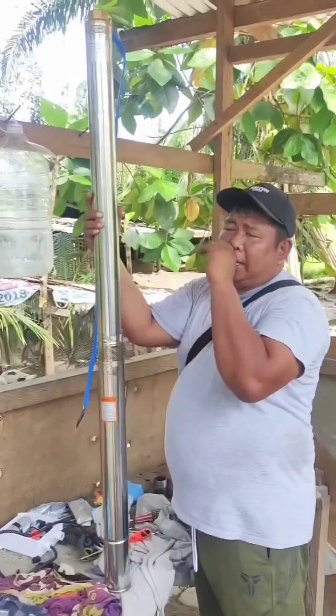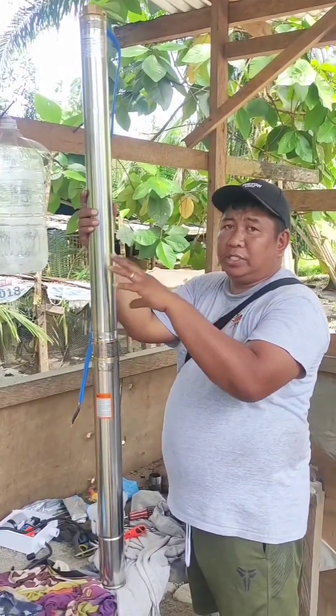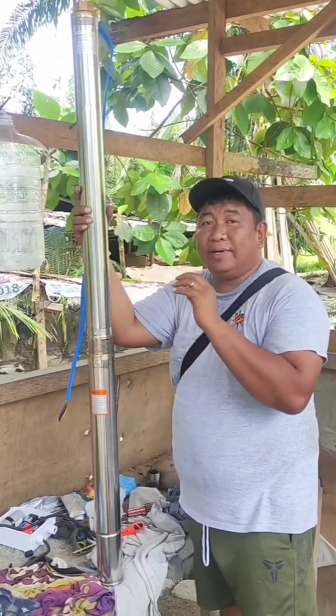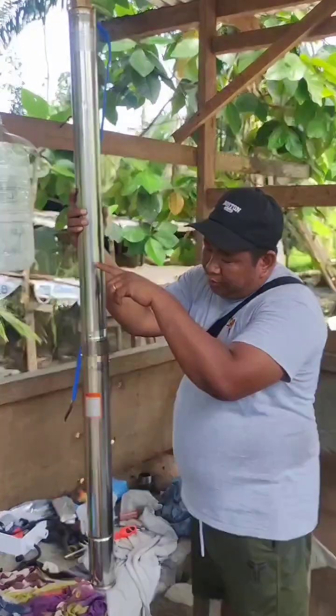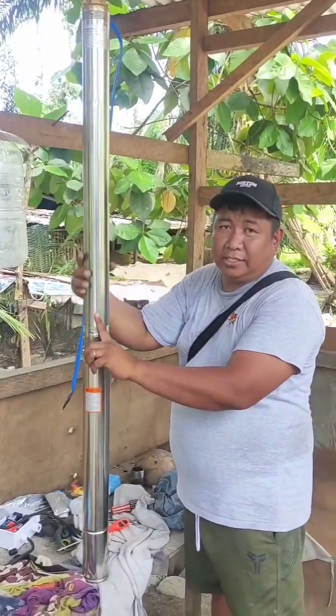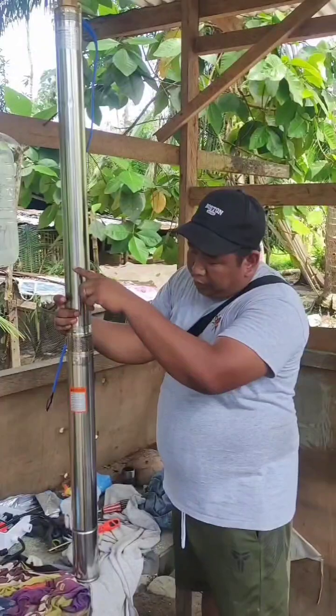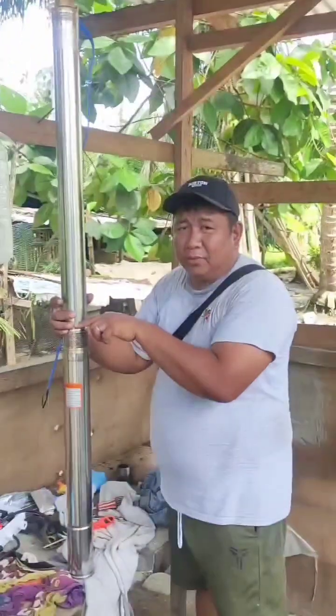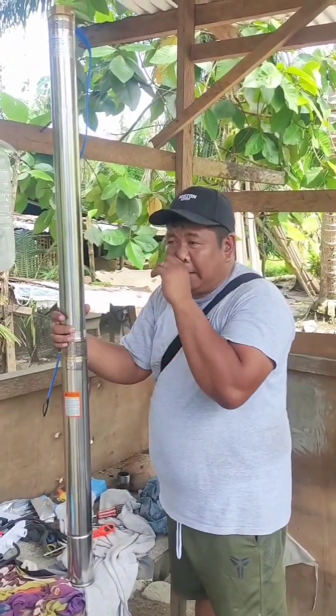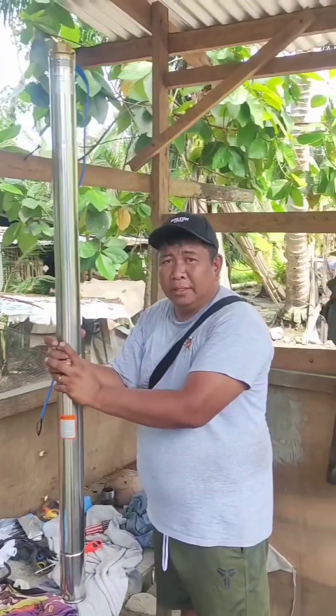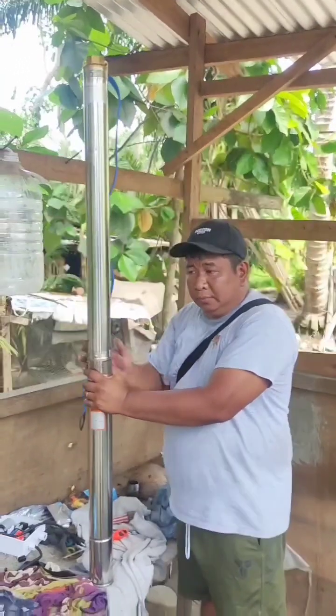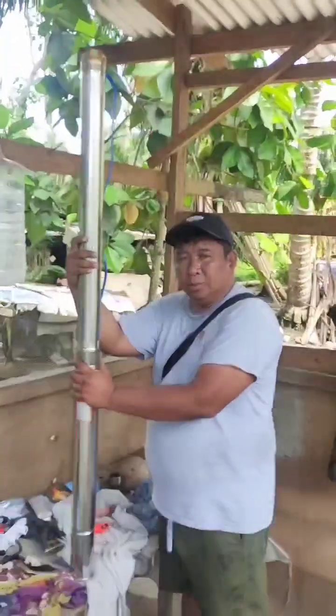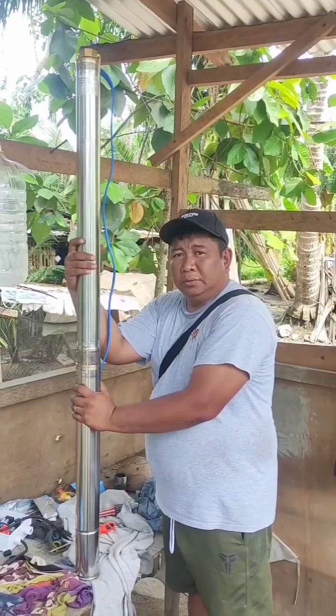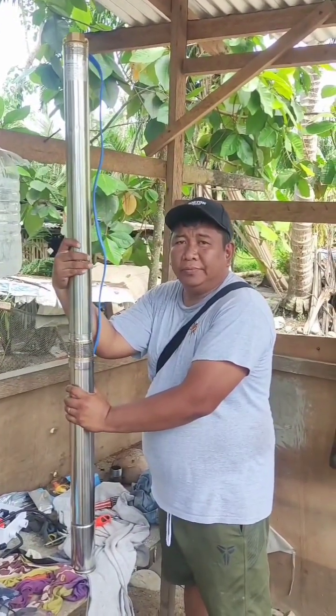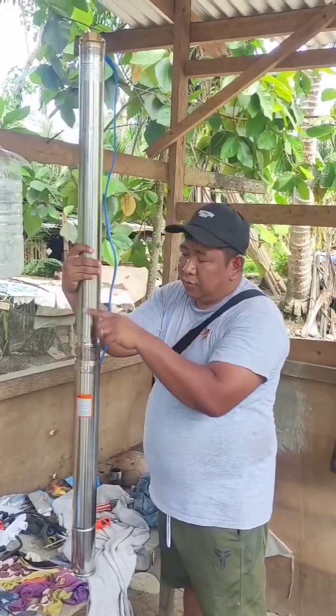We make a switch there with the floatless relay. So there is a probe here, that's the sensor. When the water drops to this level, it would automatically stop. Okay, so it has two sensors. When the well is dry, it will automatically shut down the power due to the heat, and the other one is due to the water level.